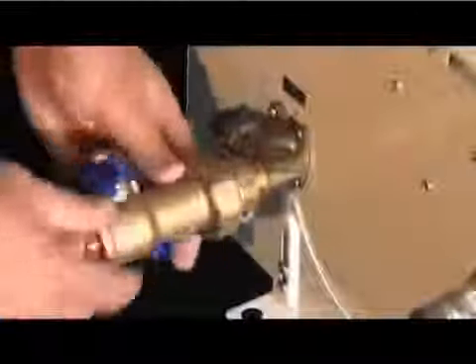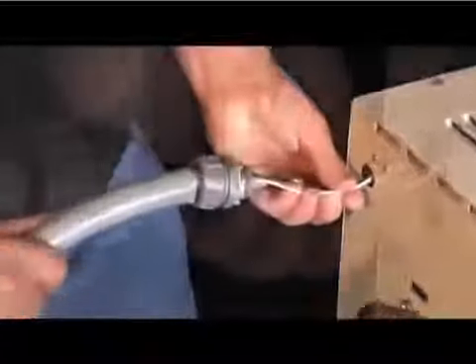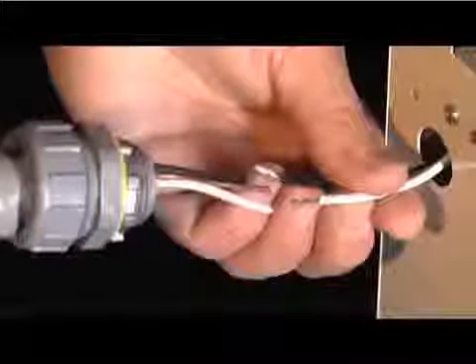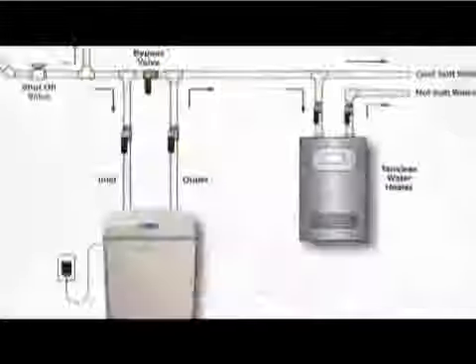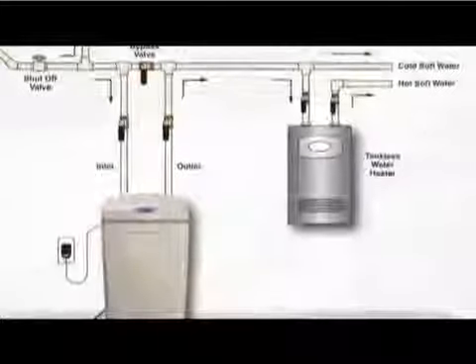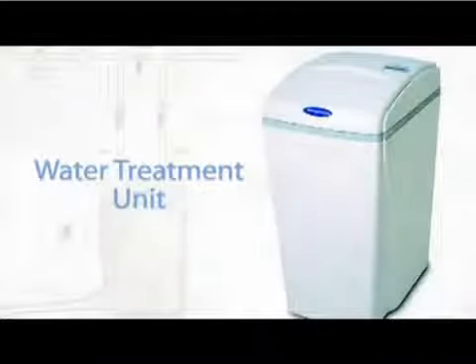The water supply line typically connects to the bottom of the tank, as does the delivery or outgoing line. On this exterior unit, the dedicated line for propane also connects at the bottom of the cabinet. The unit also requires electricity and control wiring to operate its electronic components. For any type of water heater, it also is a good idea to treat any water source that's mineral rich or of poor quality. Doing so extends the life and performance of the unit.